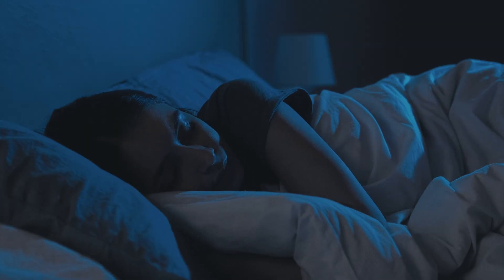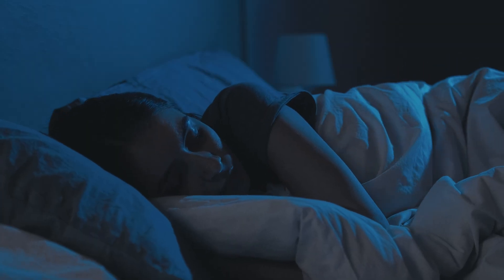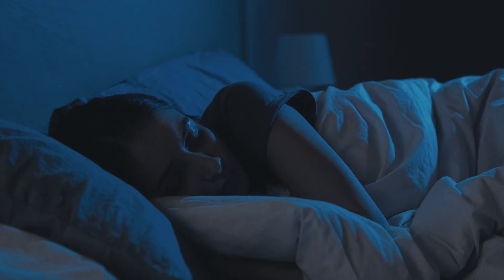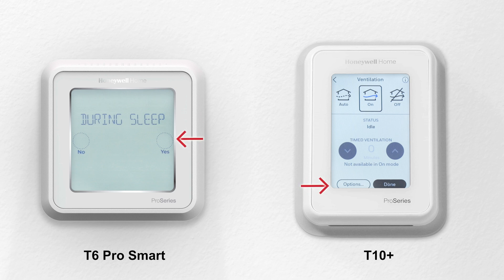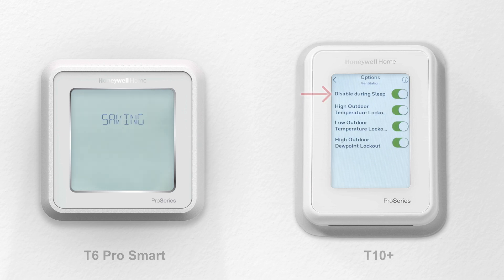When using this option, it's recommended you increase the CFM to meet ASHRAE ventilation standards faster. The ability to lockout ventilation during sleep periods isn't an option when ASHRAE is priority. However, when lockouts take priority, homeowners can use the Ventilation menu to lockout ventilation during sleep periods.